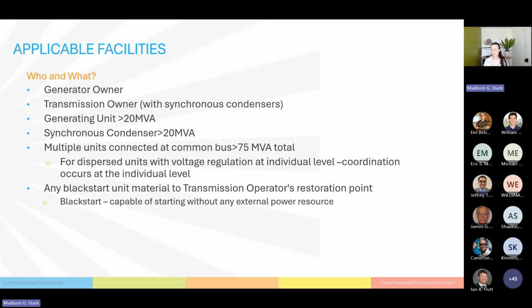Now, if you have dispersed generation, but you have multiple units that are aggregated to over 75 MVA total, that counts as well. With these dispersed units, the coordination applies at the individual level rather than at the common bus. Well, it's kind of both: you have to have individual level coordination as well as common bus level coordination for those aggregate type configurations.